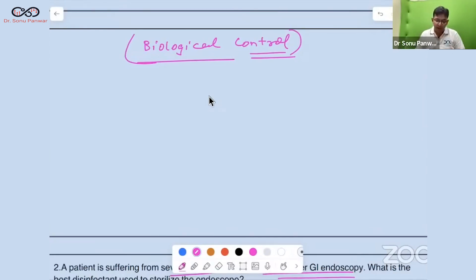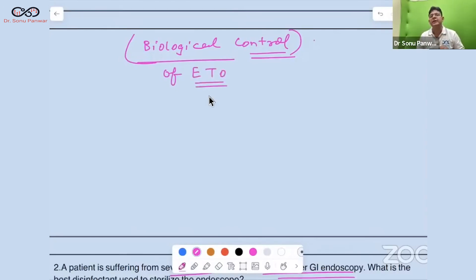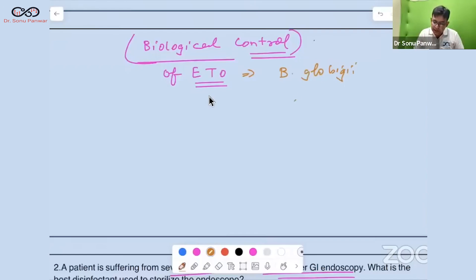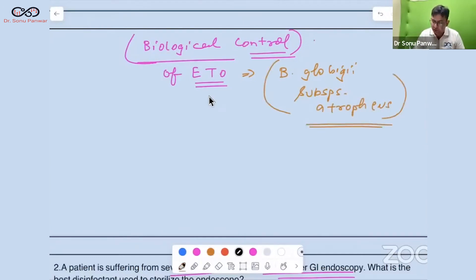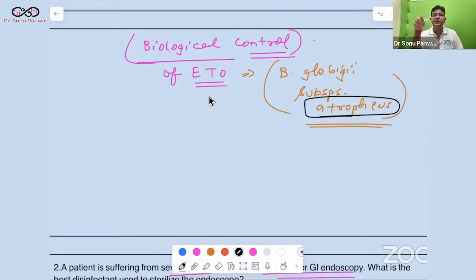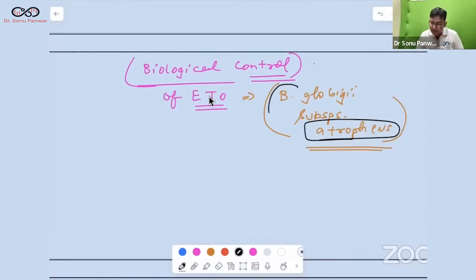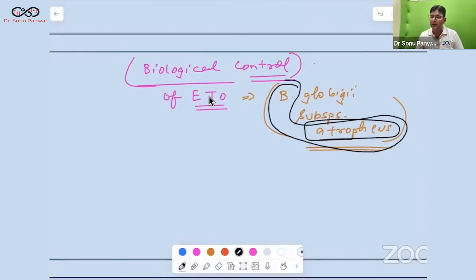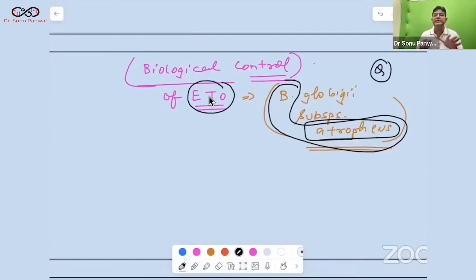Another exam question from a recent FMG exam: what is the biological control for ETO (ethylene oxide)? The biological control for ethylene oxide is Bacillus globigii subspecies atrophaeus. Note: Bacillus atrophaeus is used for both the hot air oven and ETO sterilization.